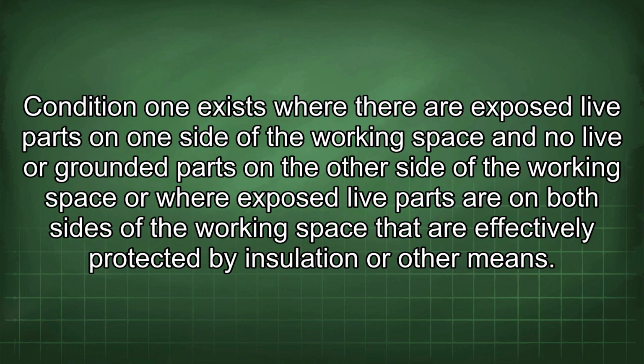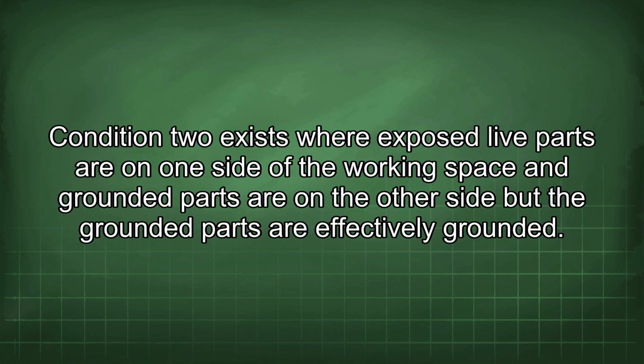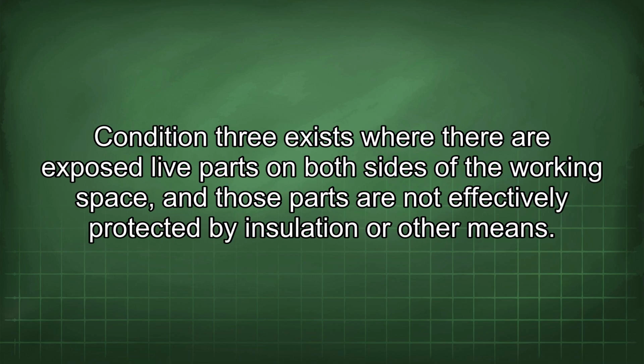Condition 1 exists where there are exposed live parts on one side of the working space and no live or grounded parts on the other side of the working space, or where exposed live parts are on both sides of the working space that are effectively protected by insulation or other means. Condition 2 exists where exposed live parts are on one side of the working space and grounded parts are on the other side, but the grounded parts are effectively grounded. Condition 3 exists where there are exposed live parts on both sides of the working space, and those parts are not effectively protected by insulation or other means.